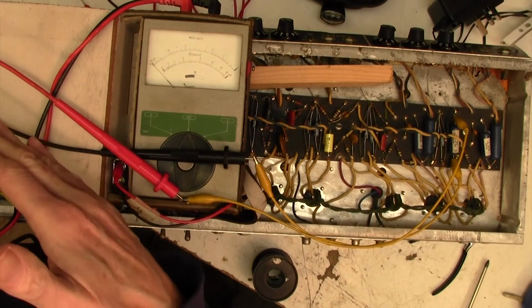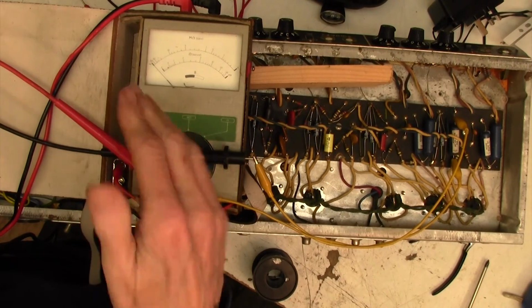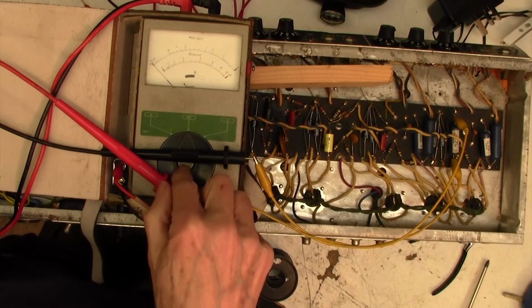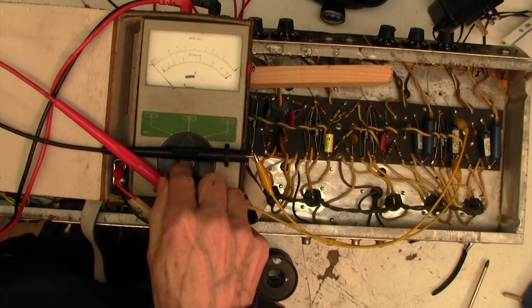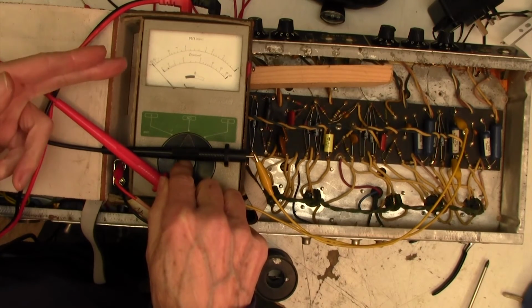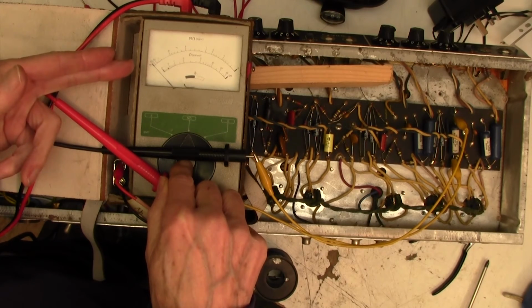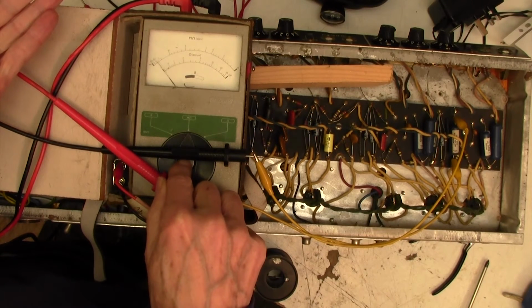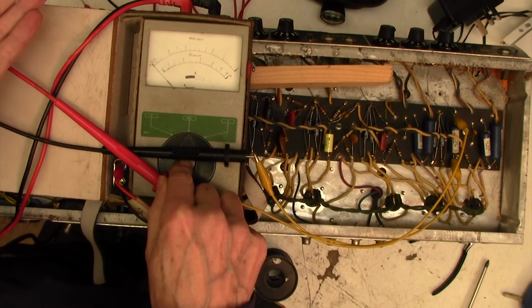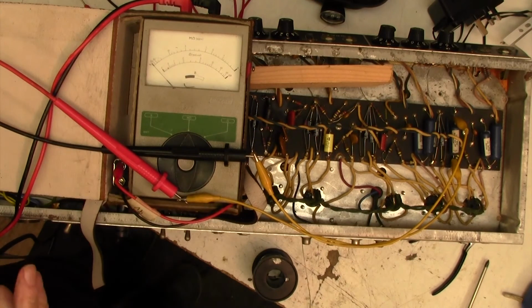Again, we'd expect to see this little blip of the meter, and then for it to settle down to in excess of 50 meg. There's the blip, and it's settled down, and again I'm closer to the meter than you are, and I can see it's not a tenth of a millimeter deviation there. So again, a perfect capacitor.